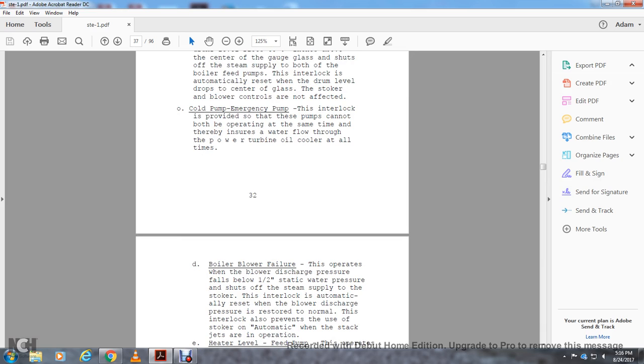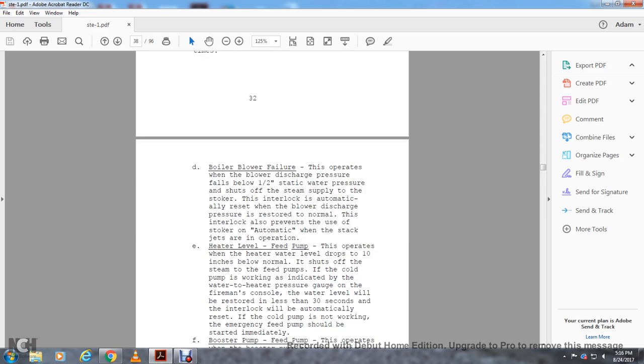Boiler blower failure. This operates when the boiler blower discharge pressure falls below 1/2 inch static water pressure. It shuts off the steam supply to the stoker, and the interlock is automatically reset when the blower discharge pressure is restored to normal. This interlock also prevents the use of the stoker automatic when the stack jets are in operation.